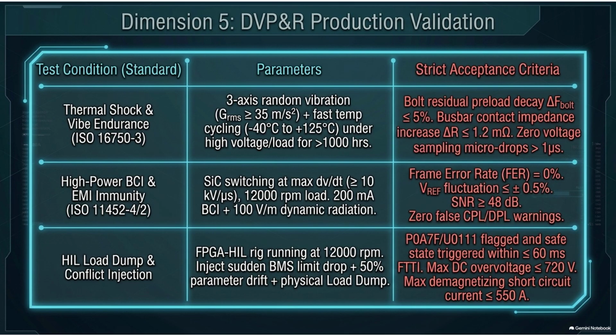Yes. The test is considered a pass only if the controller shorts the phases fast enough to ensure the internal DC bus voltage never crosses 720 volts. And the maximum short-circuit phase current has to remain under 550 amps. Proving that the architecture can autonomously absorb the kinetic energy of the motor without destroying its own power stages. Exactly. So what does this all mean for us?